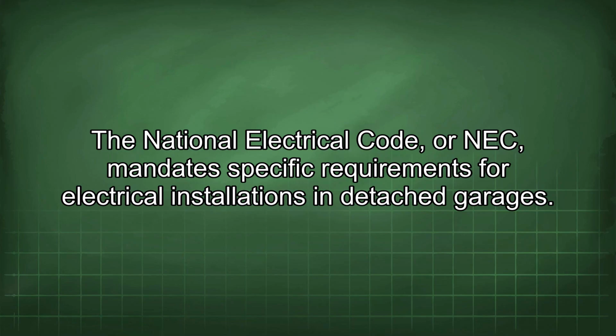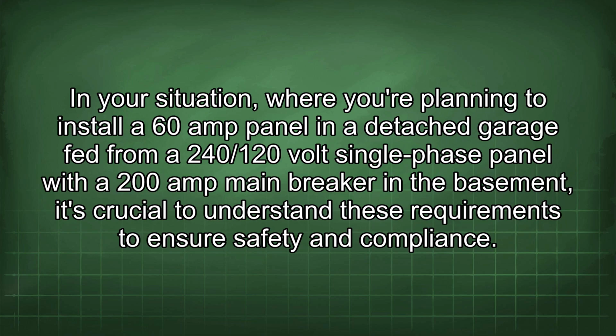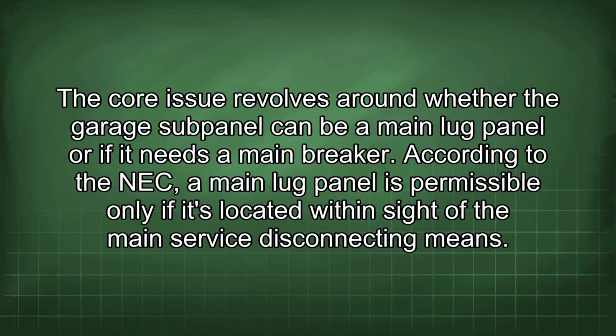The National Electrical Code, or NEC, mandates specific requirements for electrical installations in detached garages. In your situation, where you're planning to install a 60-amp panel in a detached garage fed from a 240/120-volt single-phase panel with a 200-amp main breaker in the basement, it's crucial to understand these requirements to ensure safety and compliance. The core issue revolves around whether the garage subpanel can be a main lug panel or if it needs a main breaker. According to the NEC, a main lug panel is permissible only if it's located within sight of the main service disconnecting means.